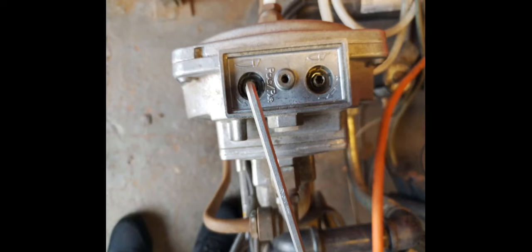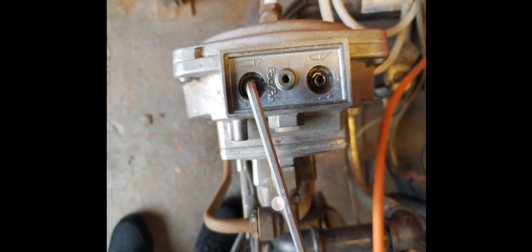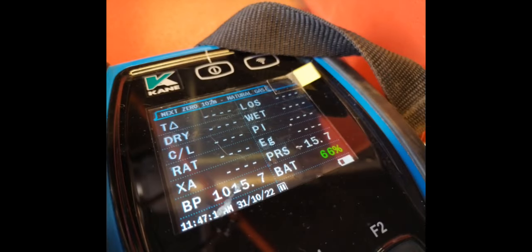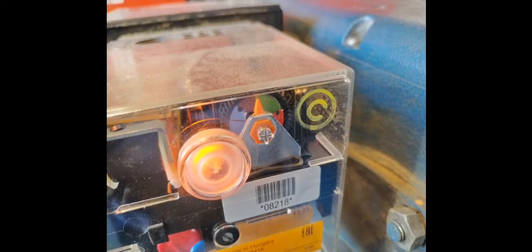And then when I made some slight adjustments, you see I've gone from here at about, say, 5 o'clock to over here at about 7, 8 o'clock. I went from 16.2 to 15.7, and then I made it back up to where I started out. Whereas when I worked on another unit, it was not working. So the gas valve was gone on this particular unit.